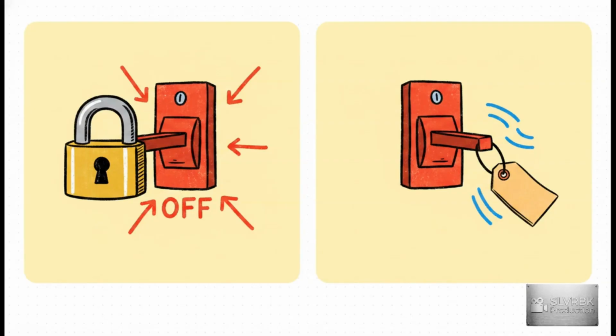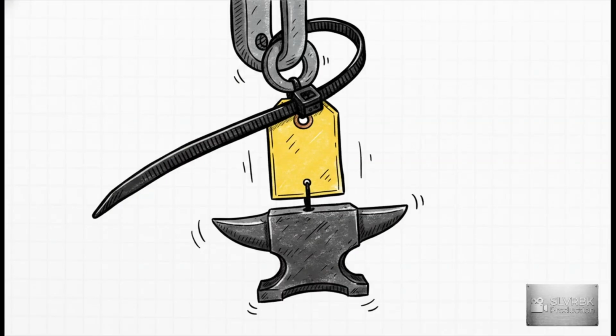Because of this, OSHA considers locks to be vastly more secure. If you use a tagout system on a machine that could be locked out, your employer has to implement extra safety measures to guarantee the exact same level of protection that a lock would have provided. And when tagout is used, OSHA leaves absolutely nothing to chance with the hardware. You can't just tie a tag on with a flimsy piece of string. The standard mandates that the tag attachment has to be non-reusable, attachable by hand, self-locking, and non-releasable. Specifically, it needs a minimum unlocking strength of no less than 50 pounds. Essentially, it needs to be equivalent to a heavy-duty nylon cable tie. There is no master key for a tagout tie. It has to be destructively cut off.